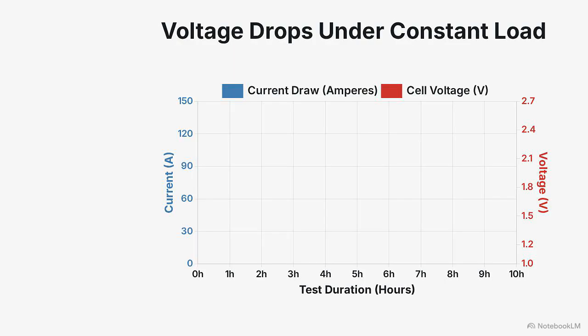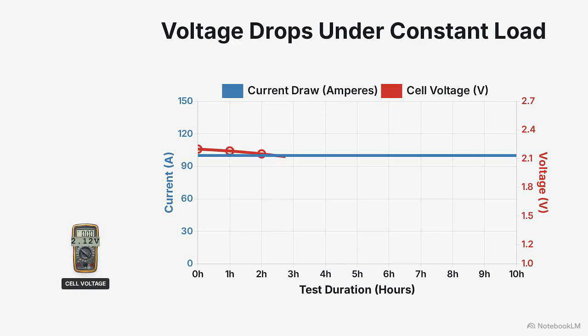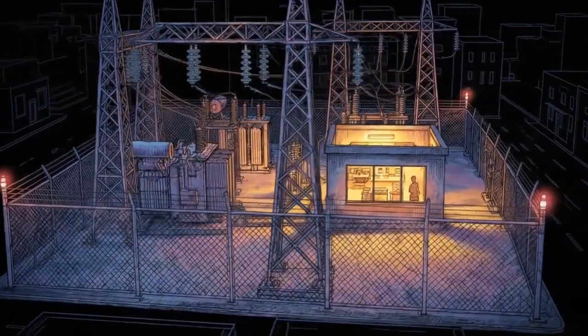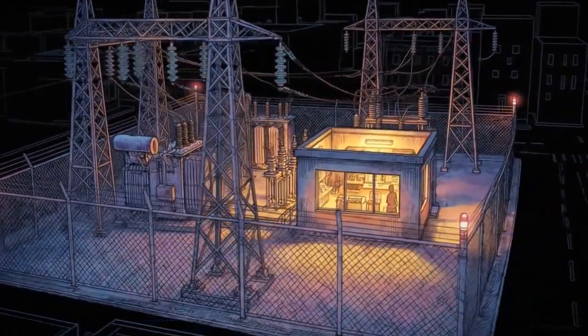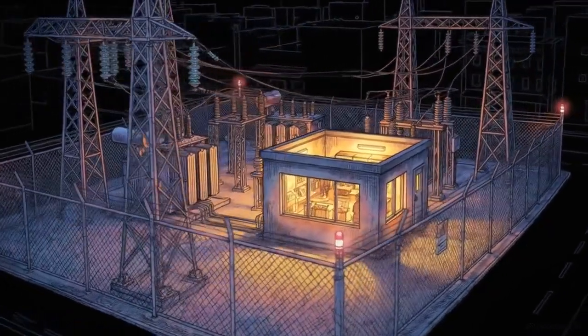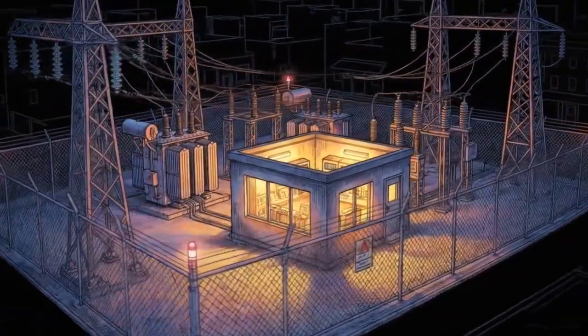During execution, the load bank pulls a constant current draw. Over the next 10 hours, technicians periodically log both the total bank voltage and the individual cell voltages as they steadily degrade. At the end of the test period, these final unit voltages are cross-referenced against the manufacturer's accepted end voltage charts. Surviving this sustained stress test provides the empirical proof that the chemical storage can independently hold the substation online during a catastrophic blackout.